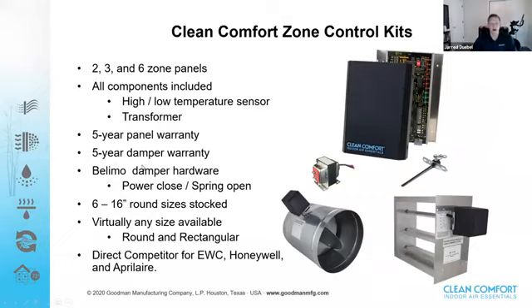Okay, now this is our economy zone control panels and kits. Again, they're all going to come in kits just like the ESP. You're going to have the 2-zone, the 3-zone panels, and then the 6-zone expandable up to 12. We also offer the 2-wire more standard type dampers with those zone control systems, but you can put 3-wire dampers on those systems. The most notable feature between the ESP and the economy line is that you need to regulate static pressure with the economy line by means of a bypass damper or some other means, because you're not going to have that static pressure sensor.